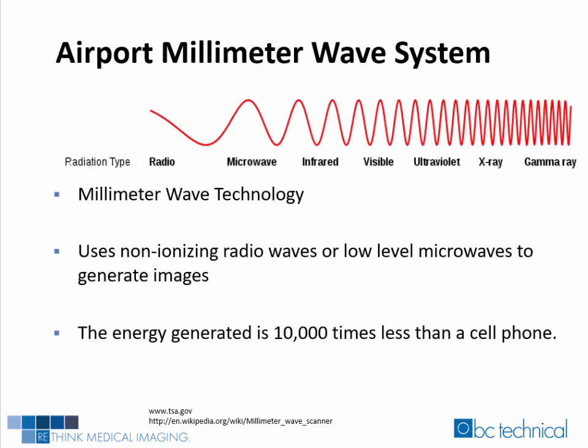The other technology used for airport screenings is called millimeter wave technology. Images are created using non-ionizing radio waves or low-level microwaves. With active scanners, the millimeter wave is transmitted from two antennas simultaneously as they rotate around the body. The wave energy reflected back from the body or other objects on the body is used to construct a three-dimensional image, which is displayed on a remote monitor for analysis. The energy generated from these systems is 10,000 times less than a cell phone.